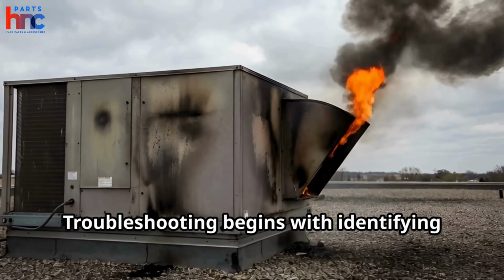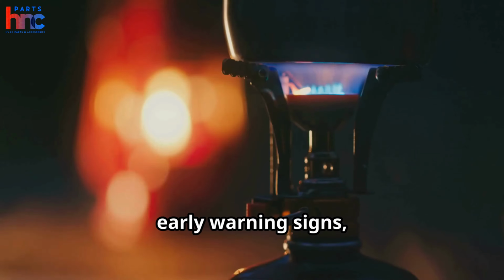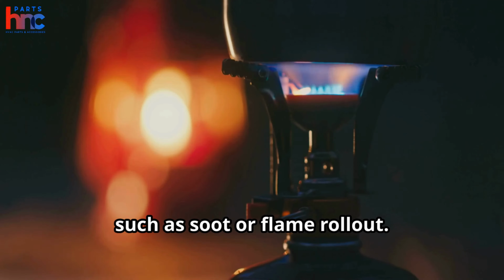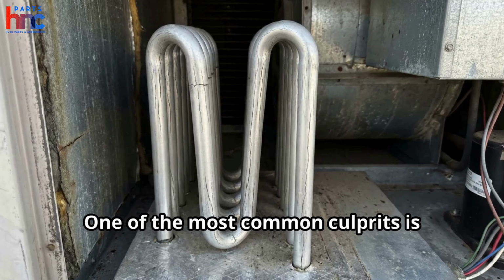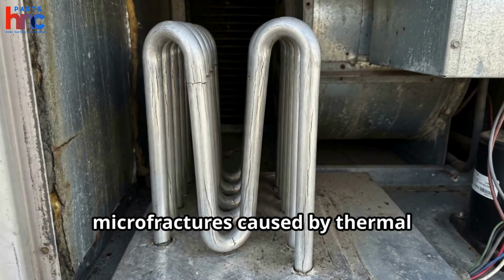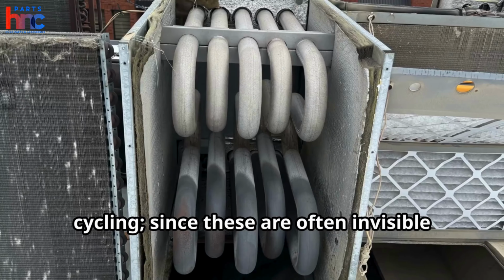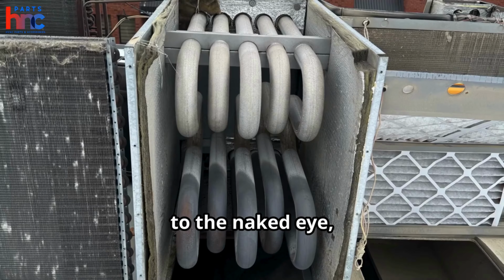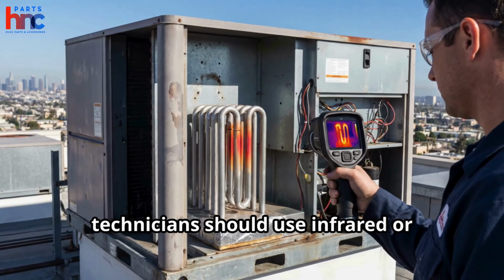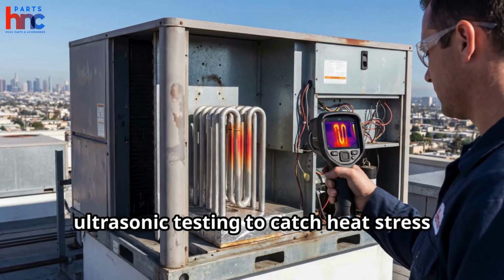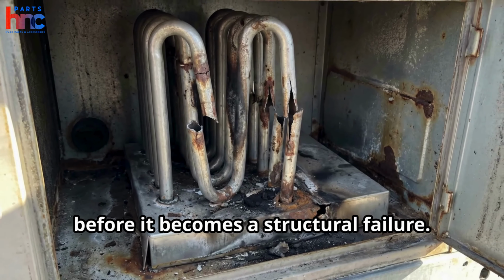Troubleshooting begins with identifying early warning signs, such as soot or flame rollout. One of the most common culprits is microfractures caused by thermal cycling. Since these are often invisible to the naked eye, technicians should use infrared or ultrasonic testing to catch heat stress before it becomes a structural failure.